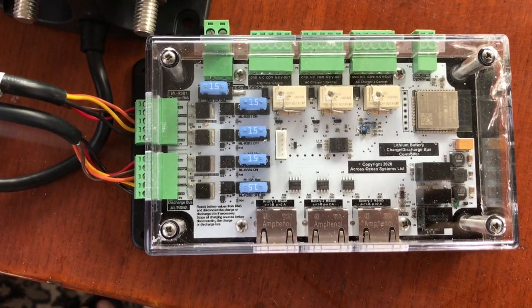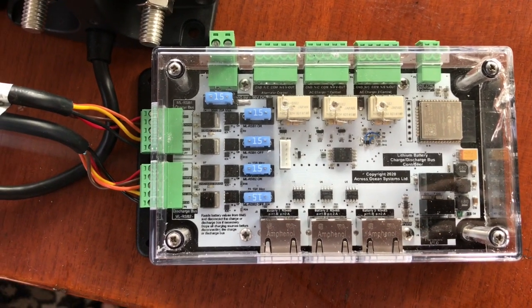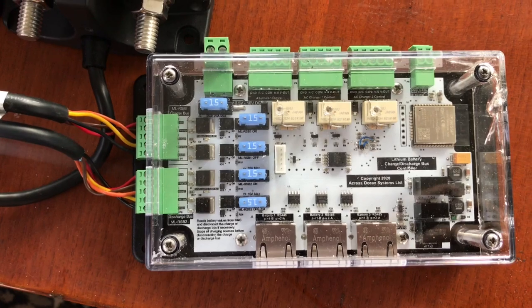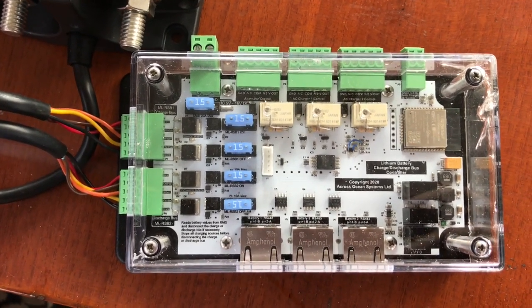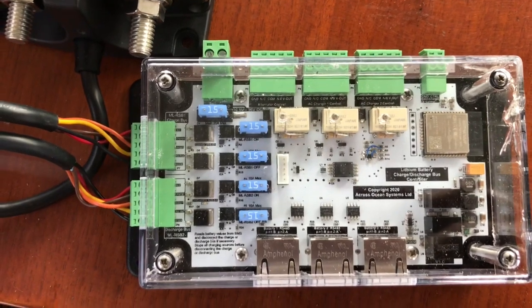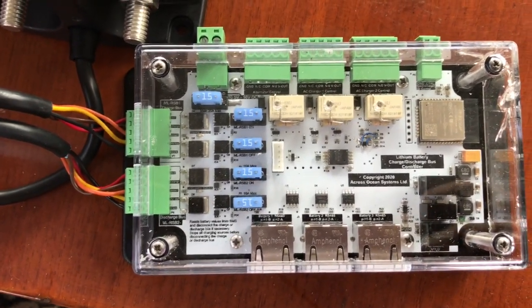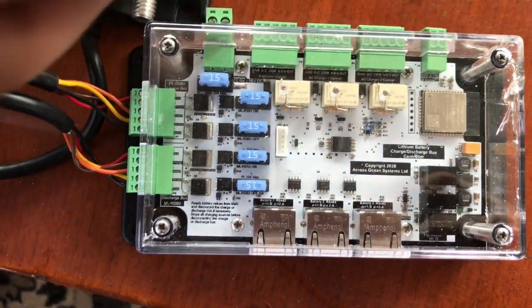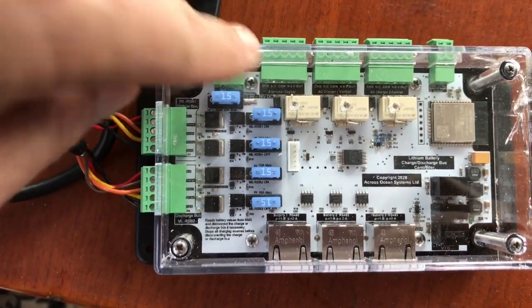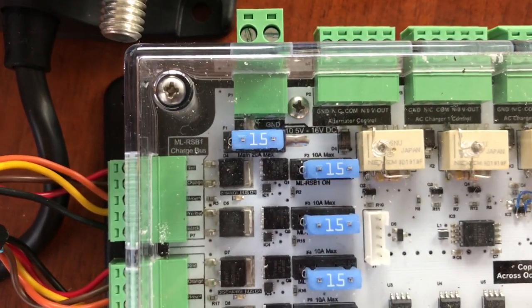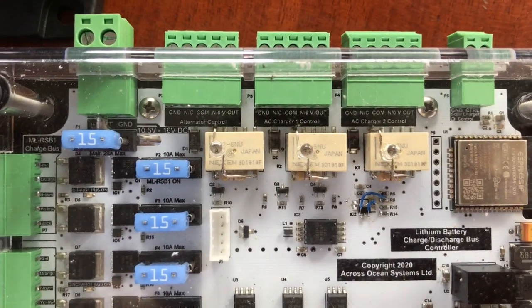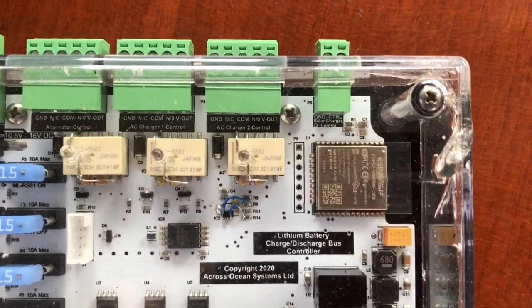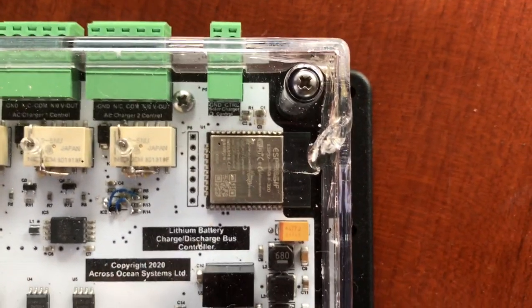And depending on the conditions, there are 2 important conditions that we have to watch for: over voltage and under voltage. So the over voltage condition, you have to stop all of the charging. So this system has charger controls: the first charger control will control my alternator, the second one will control my first AC charger, the third one will control my second AC charger, and the last one controls my solar charger.